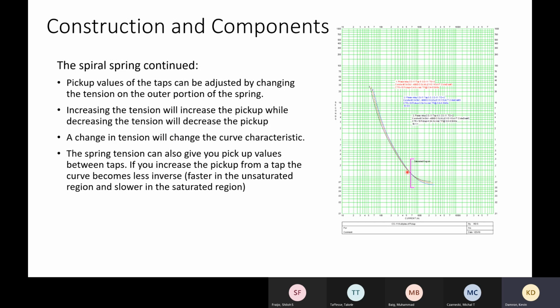So the interesting thing is a lot of that has an effect on whether you're on the unsaturated side or the saturated side of the relay. And if you plot 3 different relays, here's a CO11 with a time dial, with a little bit different values, then you can see eventually they do cross. And once they hit that saturated region, that's what actually causes them to cross.